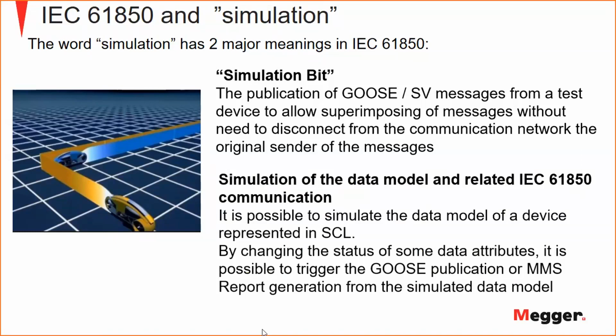without any link to the reality. The relay doesn't trip at all. There is no power system fault, but I can simulate that the trip from the relay is generated and is sent as a GOOSE message. This is a simulation, which is a very important concept because we test a SCADA system with that, for example.